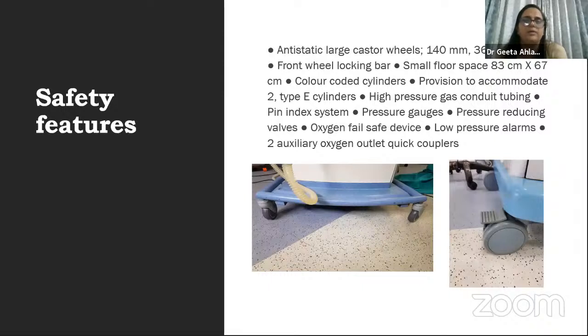If one of the wheels is broken, or if the machine is tilted to a side, your flow meter cannot show you a correct reading, and your vaporizer does not deliver what you intend to deliver. So your wheels should be absolutely good, and the machine should be straight. There should be no compromise on the wheels. They have an anti-static covering to prevent any static charges from building up between the machine and the floor. Although OT floors are also non-conducting nowadays, this is still another safety feature. It also has a front wheel locking bar, so that the machine doesn't hamper you and your movements when you are performing a procedure.